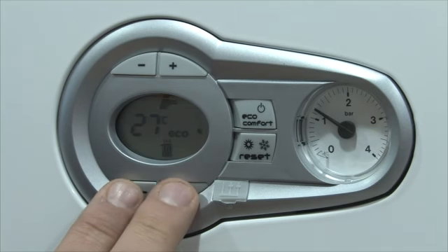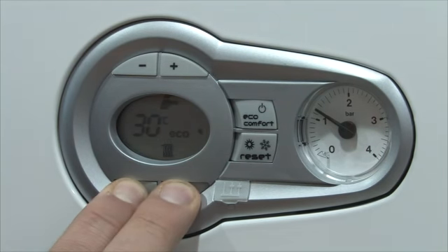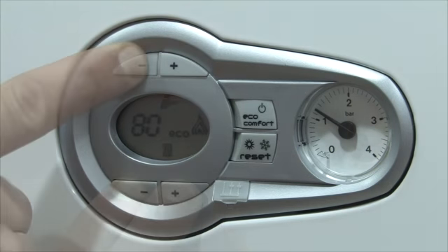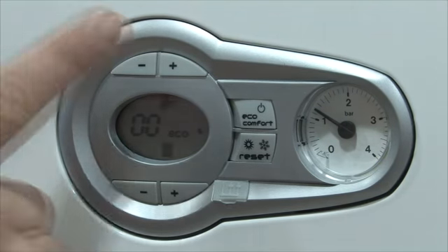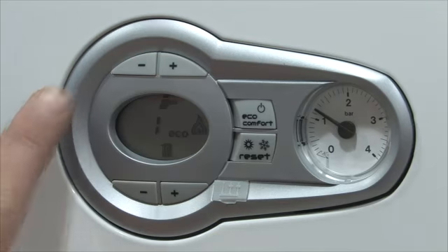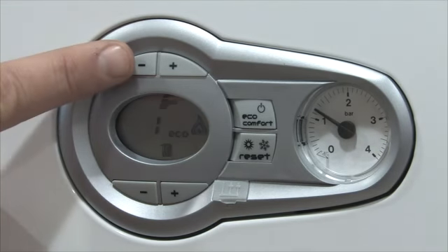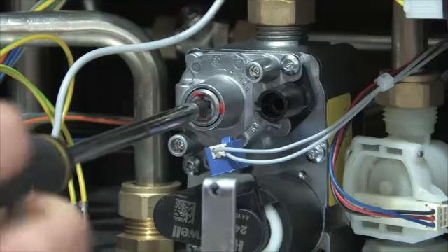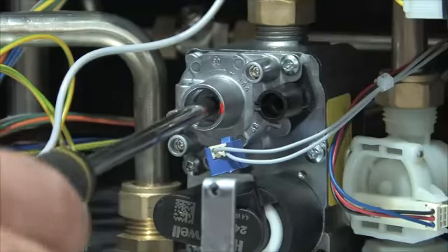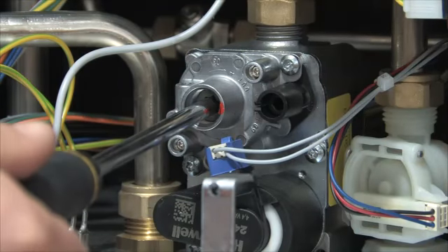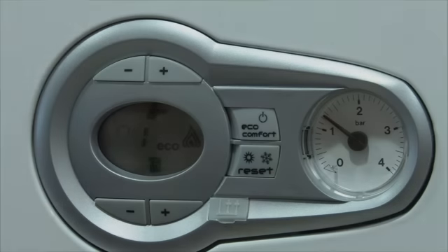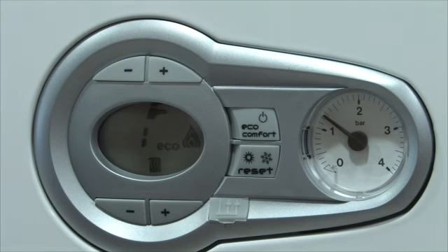Hold down the central heating plus and minus buttons for 10 seconds to enter the boiler into test mode. Use the domestic hot water plus and minus buttons to select between minimum and maximum flame. Whilst in minimum mode, remove the offset cover plate with a Torx 40 screwdriver and adjust the offset adjustment screw clockwise to increase. Press the domestic hot water plus button to enter the boiler into maximum mode.